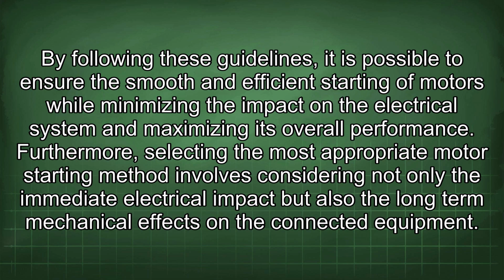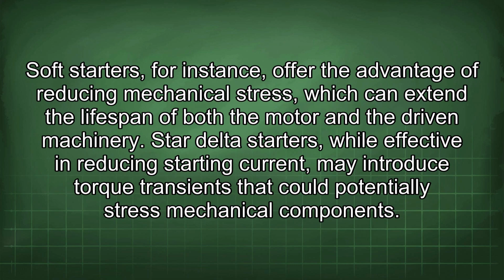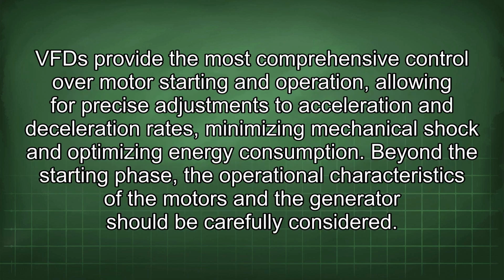Furthermore, selecting the most appropriate motor starting method involves considering not only the immediate electrical impact but also the long-term mechanical effects on the connected equipment. Soft starters, for instance, offer the advantage of reducing mechanical stress, which can extend the lifespan of both the motor and the driven machinery. Star-delta starters, while effective in reducing starting current, may introduce torque transients that could potentially stress mechanical components. VFDs provide the most comprehensive control over motor starting and operation, allowing for precise adjustments to acceleration and deceleration rates, minimizing mechanical shock and optimizing energy consumption.